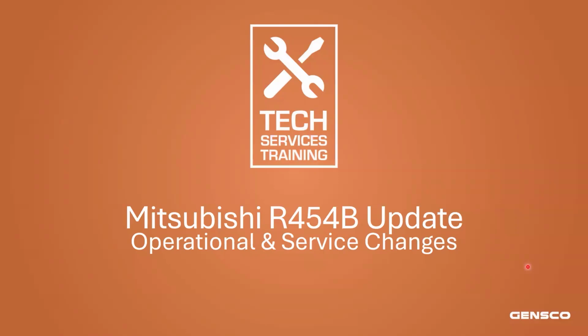I was told the engineers at Mitsubishi have this worked out. So I'm sure they wouldn't let that product go out the door if they thought the liquid line was too small. So it's engineered, it's producing what they want it to. So it is what it is, until they put a bulletin out there and say the liquid line should be 3/8. Just kidding.